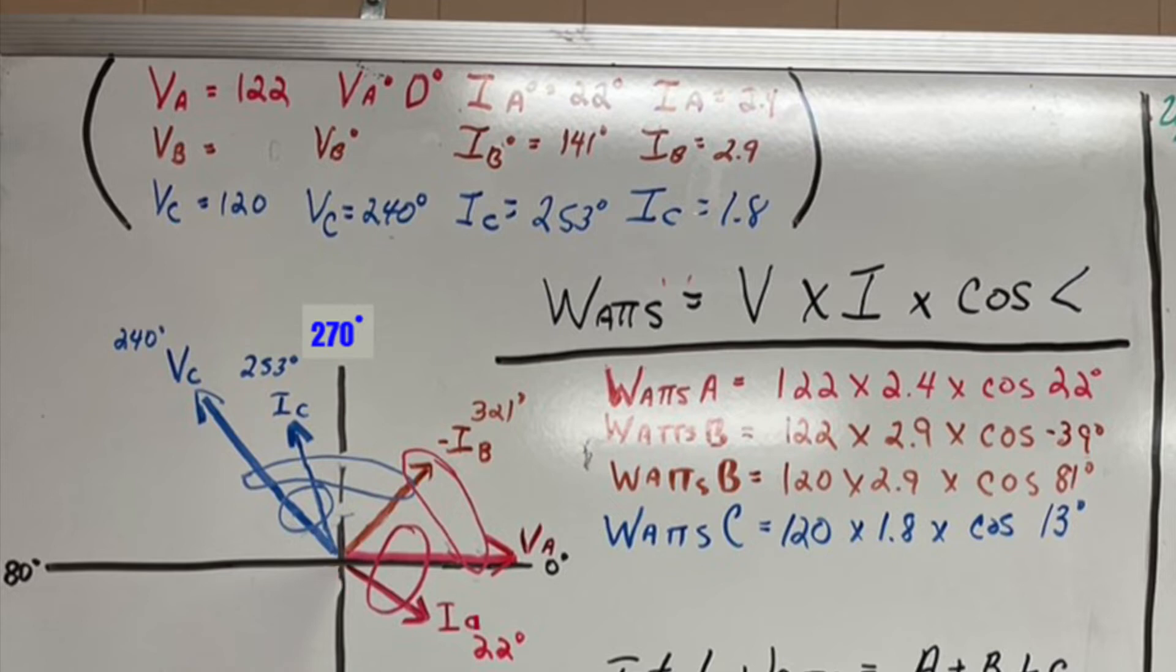So now we have B figured out. Now we're going to go ahead and do C phase. C phase is simple because you're just going to do the voltage and the current and make a little circle between the voltage C and IC. And here we have 120 volts times 1.8 times the cosine of 13 degrees.